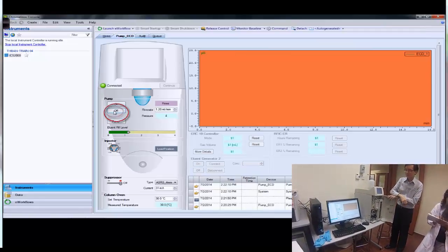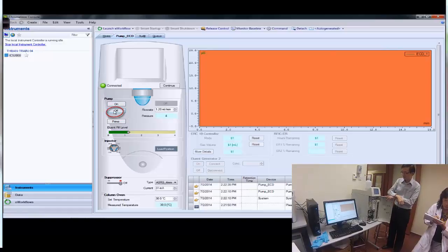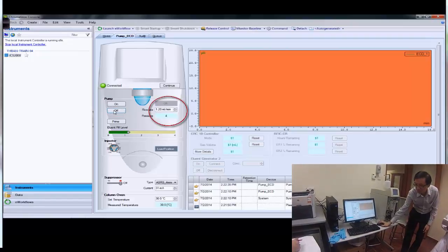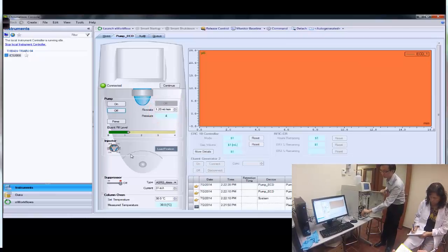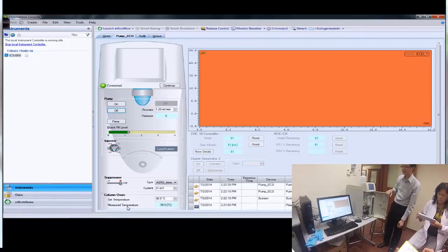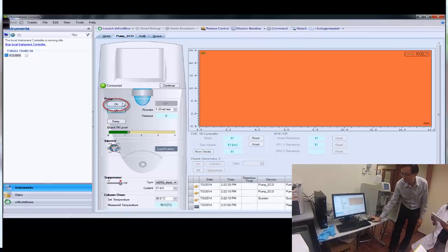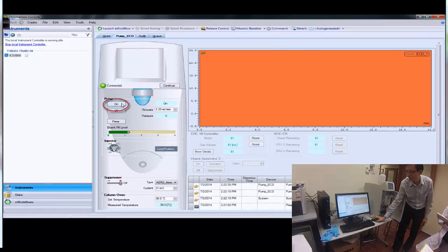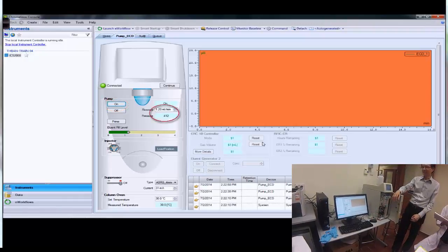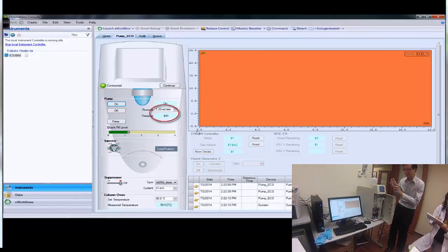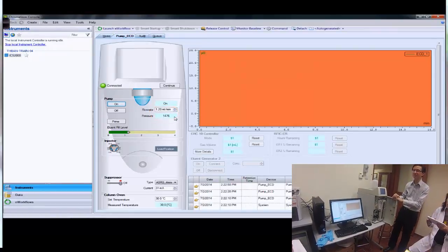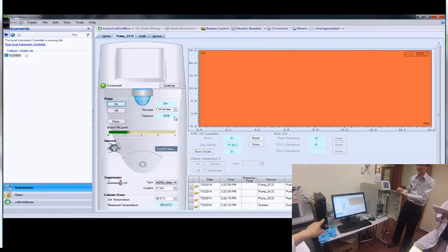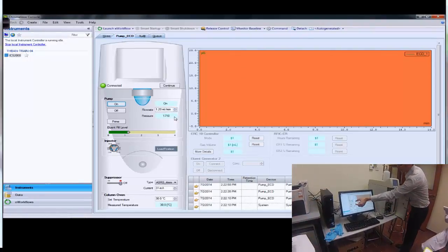When you see no more bubbles, then select the pump and turn it off, and you'll watch the pressure will be quite low at this time. Check that the flow rate is at 1.2, and then click the on button, and you should see the pressure on the right go up to somewhere around 1700-1800 psi. Let this settle for a few minutes, but record this pressure in your notebook.